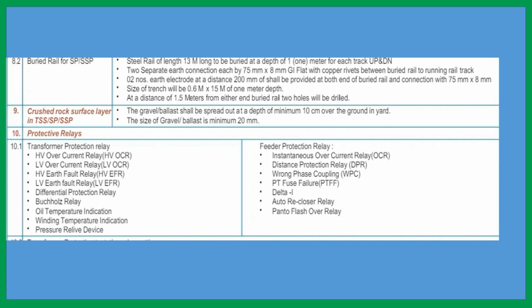Already we have studied it. The HV overcurrent relay: one is IDMT and one is instantaneous. LV overcurrent relay: one is for the transformer, it is IDMT, and the LV overcurrent relay for the feeder side is instantaneous. The earth fault relay, both sides HV and LV, we are providing earth fault relay. Differential protection relay is for power transformer internal fault differential protection. Buchholz relay is also for the transformer, if gas is formed due to heating or short circuit.